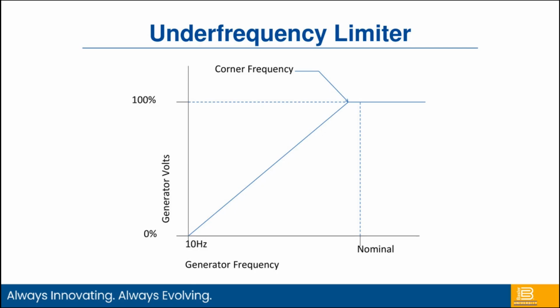There's two reasons for this. One is if I'm running at a slow speed, that machine may not be designed to operate with excitation. It's designed to dissipate the amount of heat it needs to. So we will operate at a reduced output in those conditions, so it allows the proper amount of airflow. Typically they're designed to run at their nominal frequencies. If I'm lower, I don't want to put a lot more heat into that machine and potentially damage it.